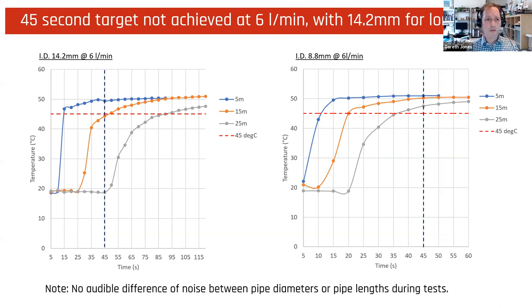Whereas if you step to a smaller diameter, on the right we've got an internal diameter of 8.8 mil, and you are actually managing to hit 45 degrees even when you're going out to 25 meters. Interestingly, when we brought lots of people to site to listen, there's no audible difference in pipe noise between these two different tests. So that's really quite important.